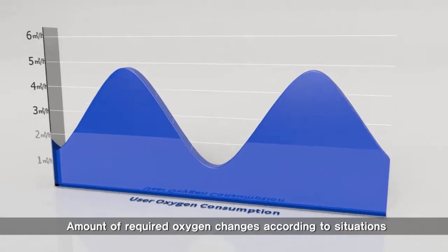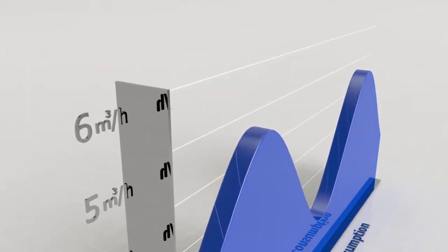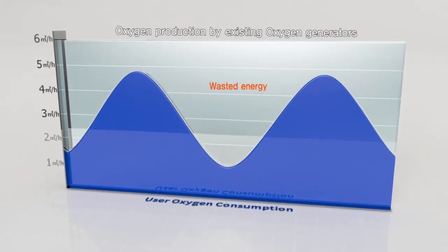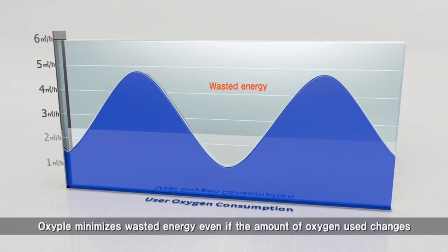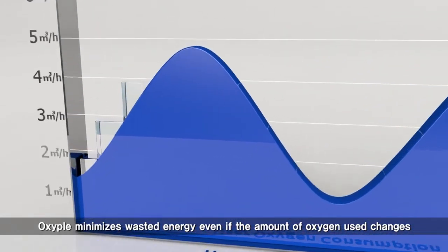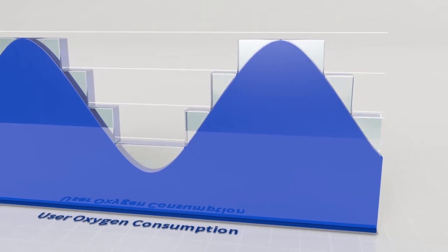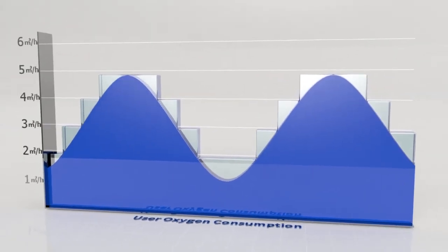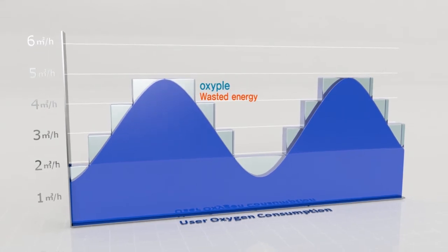The amount of required oxygen changes according to situations. Previous oxygen generators uniformly produced oxygen according to given capacity, therefore producing wasted oxygen. The Oxyple minimizes wasted energy even if the amount of oxygen use changes, thanks to its proportional control function according to amount of usage, as well as its modular product structure — unique strengths of the Oxypole.